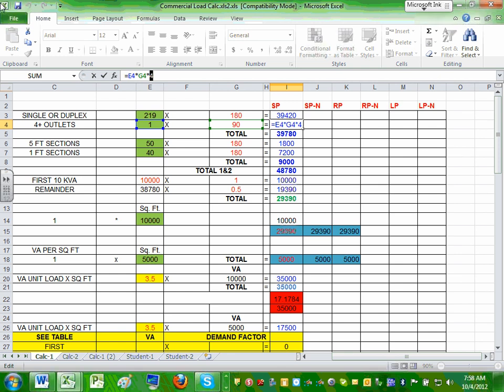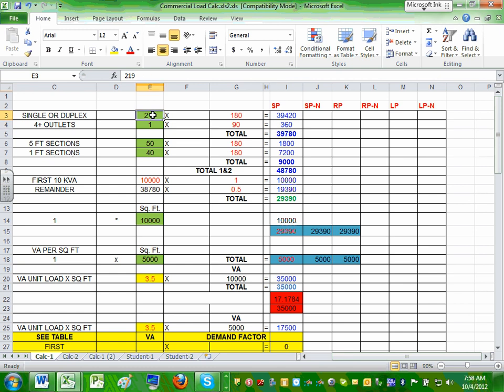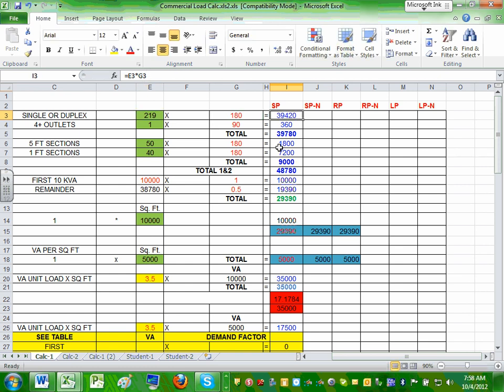Why four? Because the quad has four receptacles in it. These are hypothetical numbers, close to what we're going to have. So I have 219 receptacles at 180, which gives 39,420 volt-amps. And I have one quad at 90 multiplied by 4, giving 360. Then I added them up. That's basically for the receptacle.